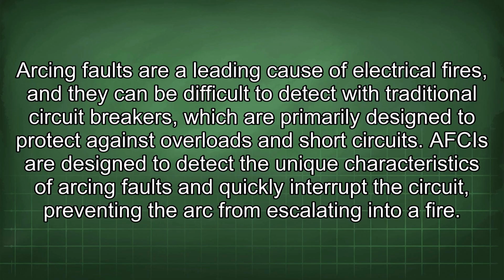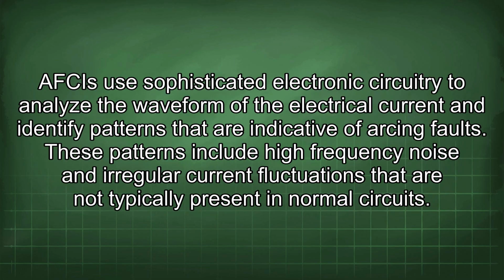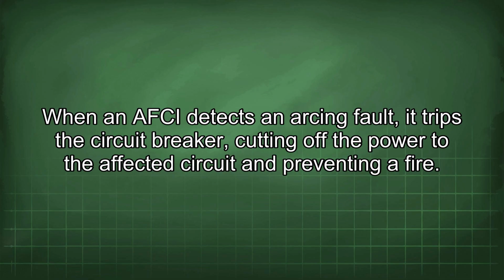AFCIs are designed to detect the unique characteristics of arcing faults and quickly interrupt the circuit, preventing the arc from escalating into a fire. AFCIs use sophisticated electronic circuitry to analyze the waveform of the electrical current and identify patterns that are indicative of arcing faults. These patterns include high-frequency noise and irregular current fluctuations that are not typically present in normal circuits.